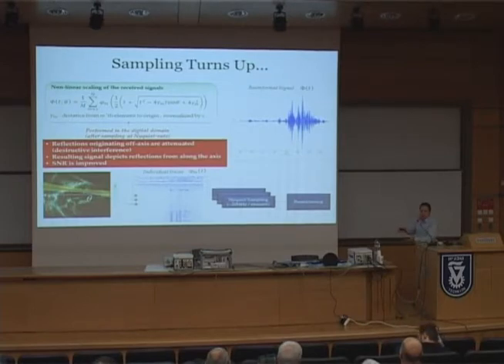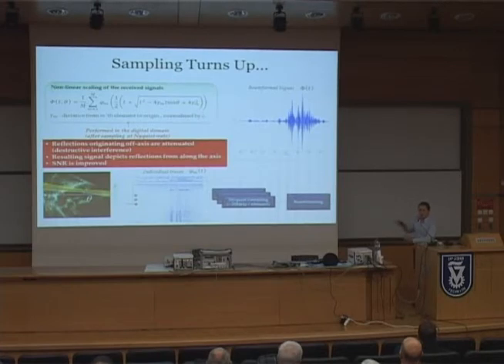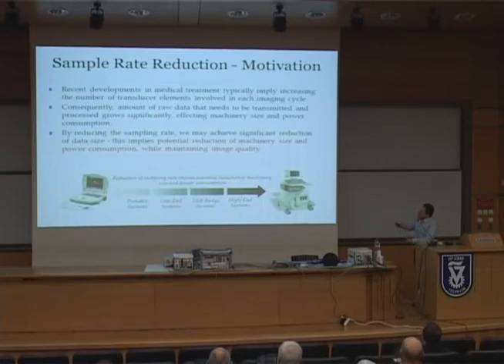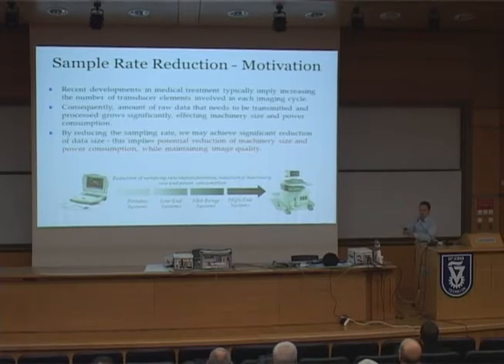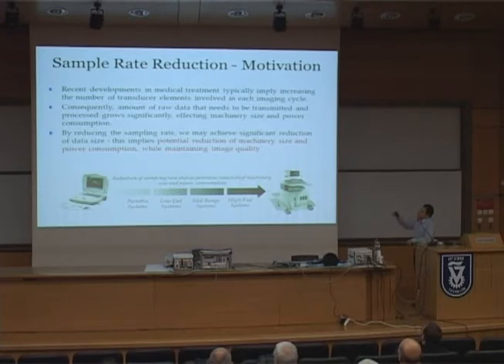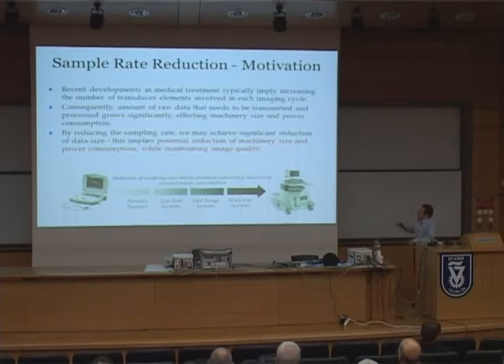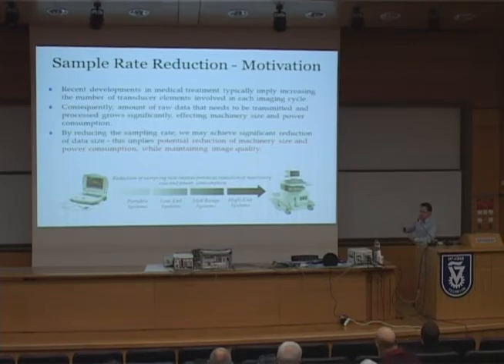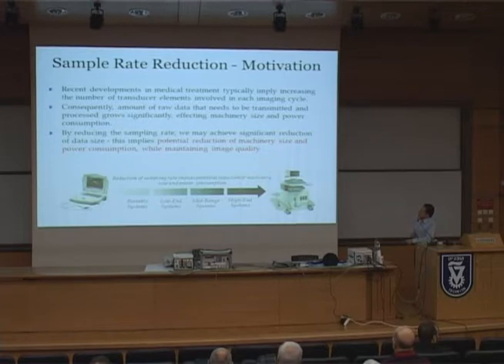20 MHz may not sound like a very high rate, but considering that this is done with a large number of elements — practically about 128 elements sampled at 20 MHz — the data volume grows significantly. With recent developments in medical imaging, the number of elements typically grows, especially for three-dimensional imaging where the array is a planar two-dimensional array of elements. Consequently, large amounts of data need to be sampled, transmitted, and processed, implying growing machinery size and power consumption. We hope that by reducing data volume, we can reduce computations, transmission, and ultimately reduce machinery size and power consumption.